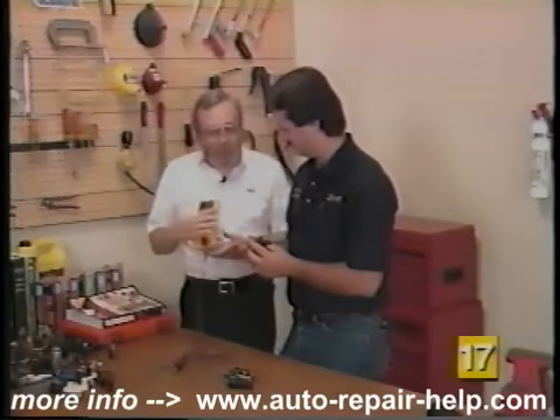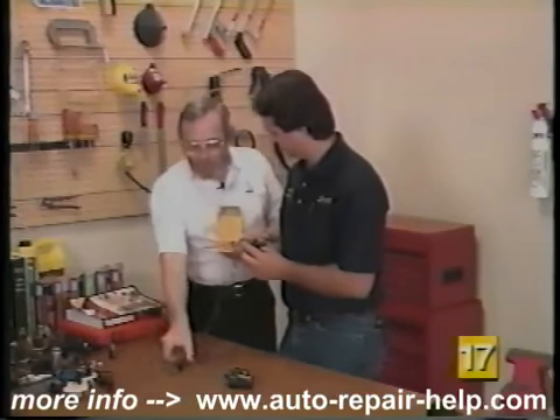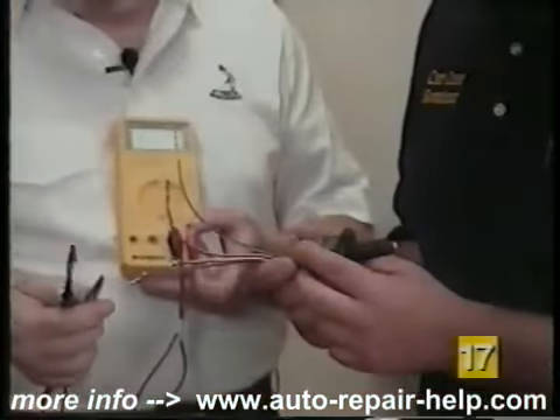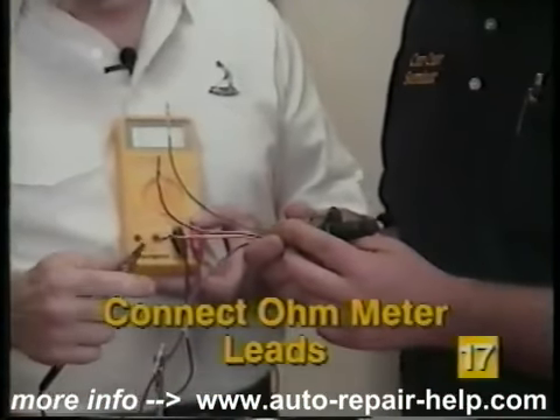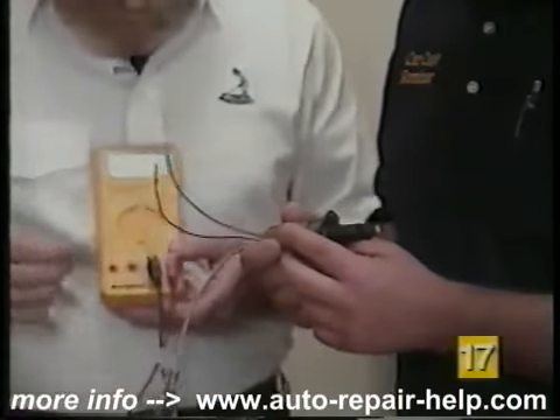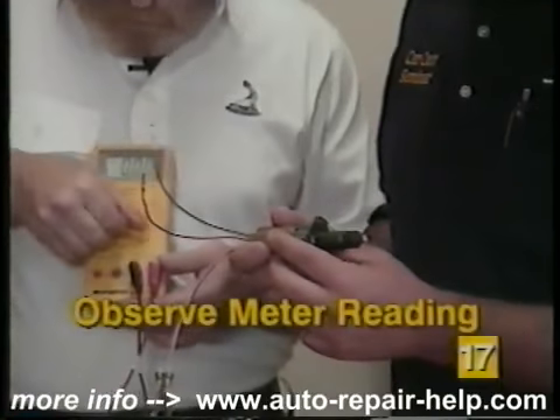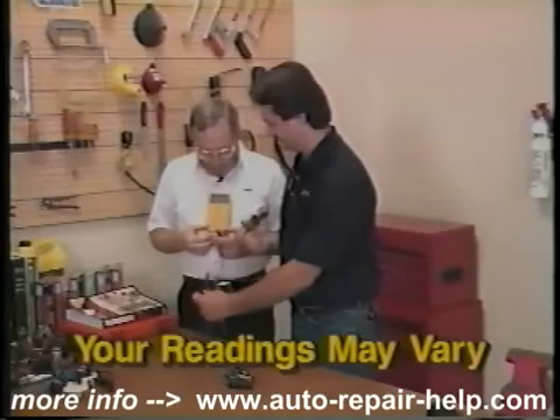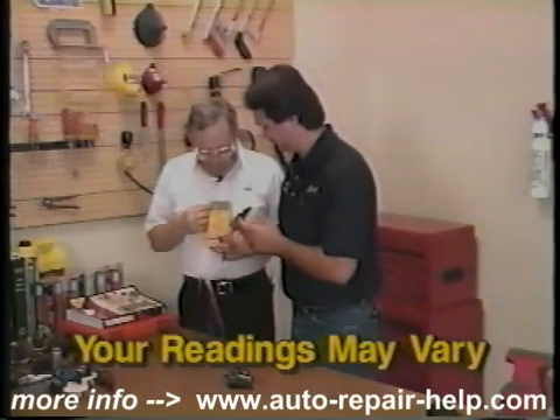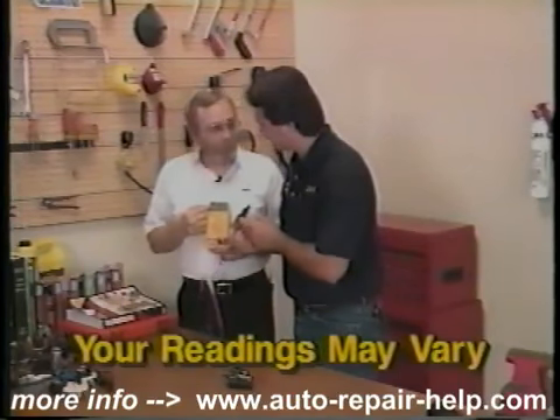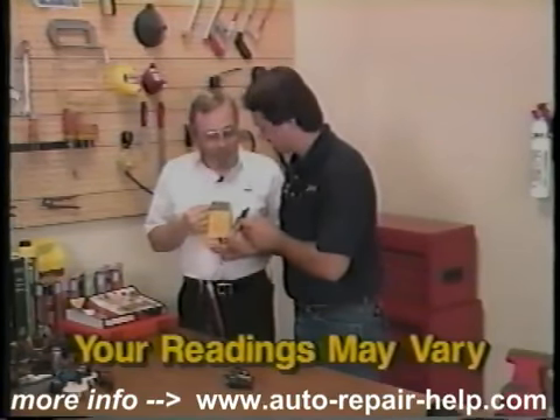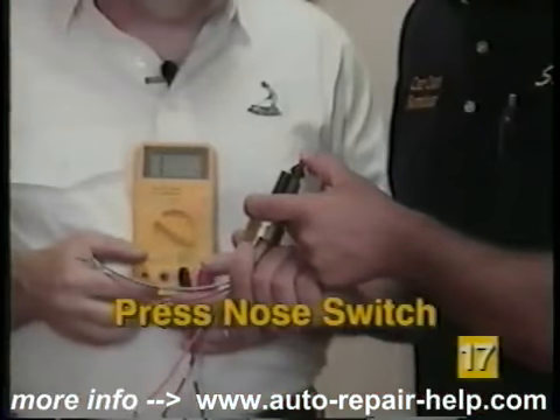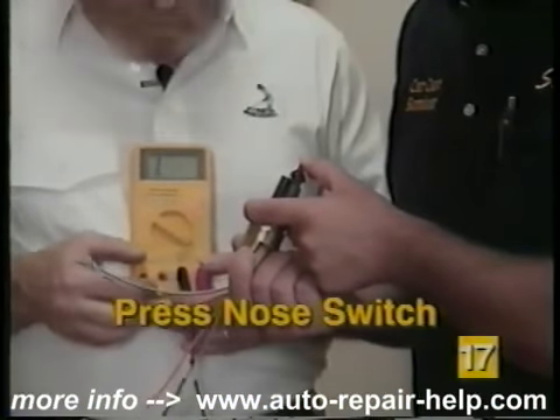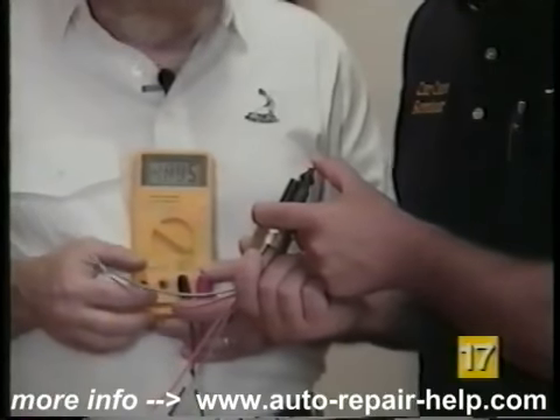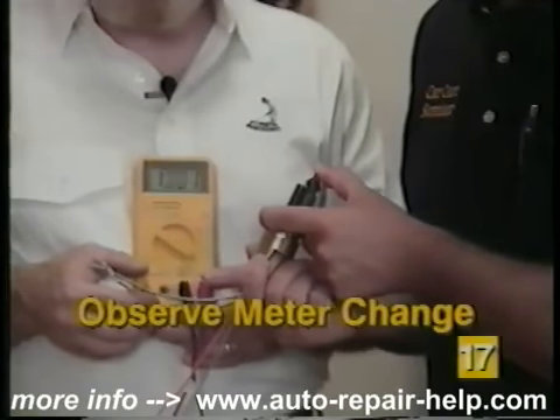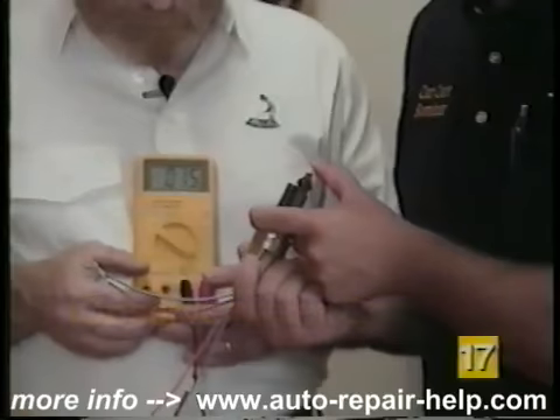And for that, I generally like to use an ohm meter. The ohm meter can be attached across the other two leads. In this case, they are orange and purple. I'll turn the ohm meter on, just most anywhere, down in the low range someplace. And that should supply us with some sort of a reading, showing continuity through the nose switch. Now, if you'll press that, the switch will open, and the reading will change to an open circuit. And every time you cycle that back and forth, it should change the meter reading.